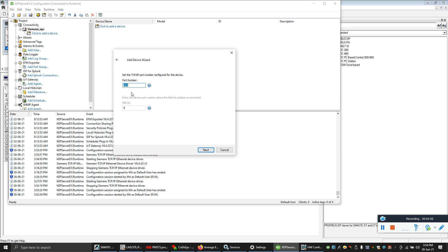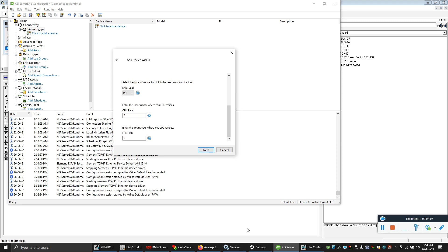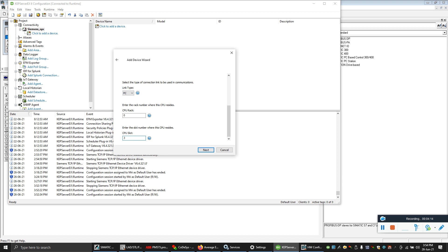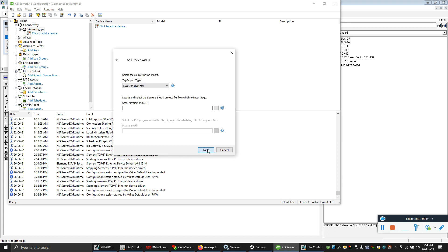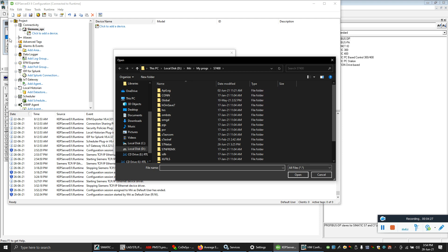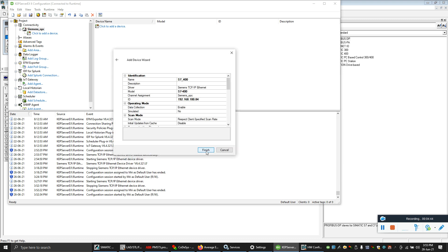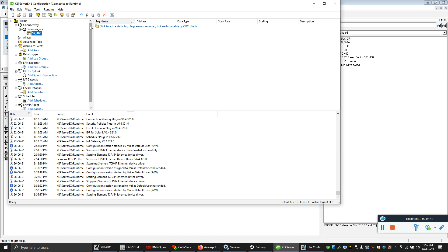Click Next, keep everything as default. The port number should be 102, which is the port number used by Siemens. Here you need to mention your CPU slot — my CPU slot is 3, so enter 3. Then you have to point to the program folder where you saved the program — specifically the .S7P backup file, which is the program backup from the same location where you downloaded the program. That's it — KEPServer configuration is done.